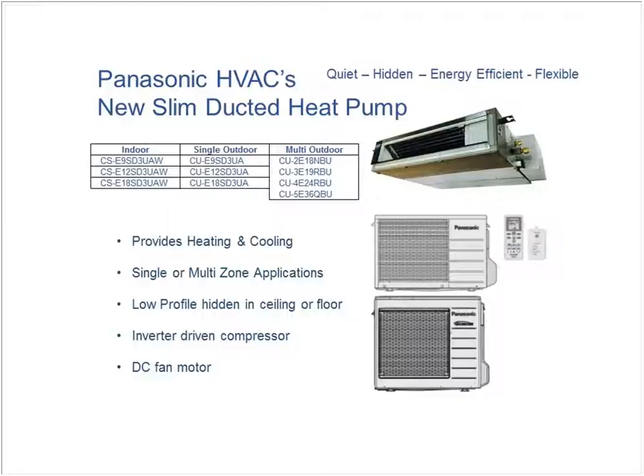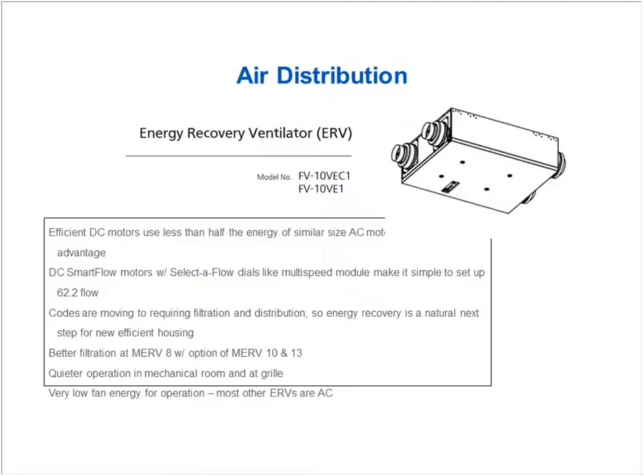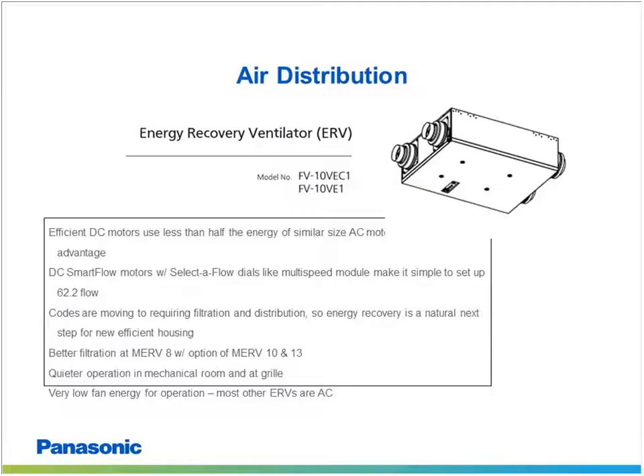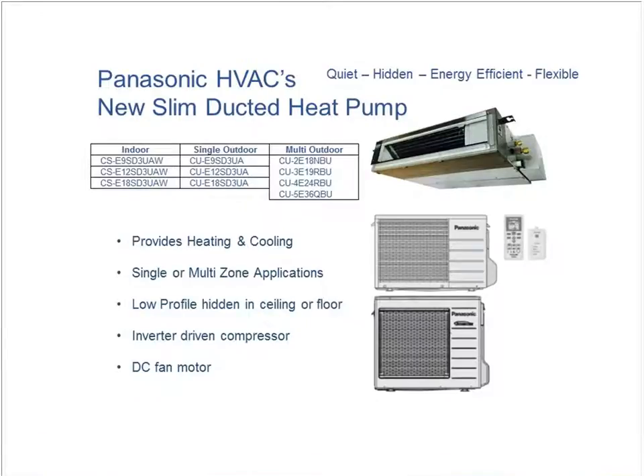They need to be a short-run duct run, but they're a duct run nonetheless. But on the inbound side, we can move and marry up the inbound air off an ERV or an HRV into that inbound side, and literally I can let that run. One of the ways that the ductless heat pumps work is they have thermistors on the supply, where the supply air comes in, so that the ductless always measures the air temperature coming into that indoor coil. So if that indoor coil temperature is up or down or sideways, it modulates and adjusts.